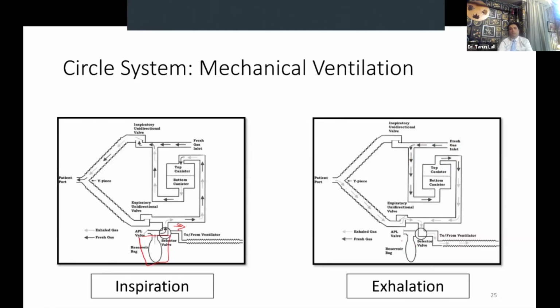What was happening earlier with the bag, now the same kind of flows will start happening with the ventilator. So the gases will flow from here to the ventilator during exhalation, and during inhalation, they will take this route, which we have shown here in the diagram on the left, and they will reach the patient.